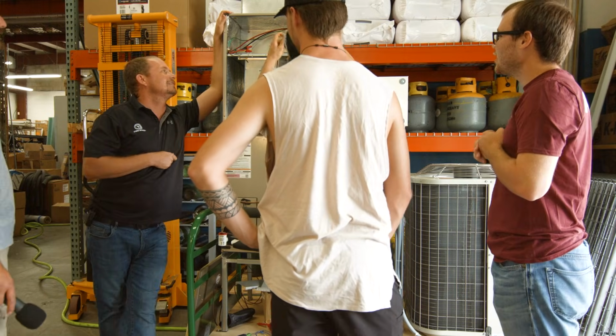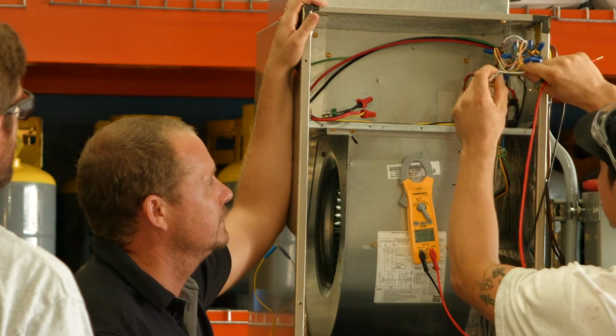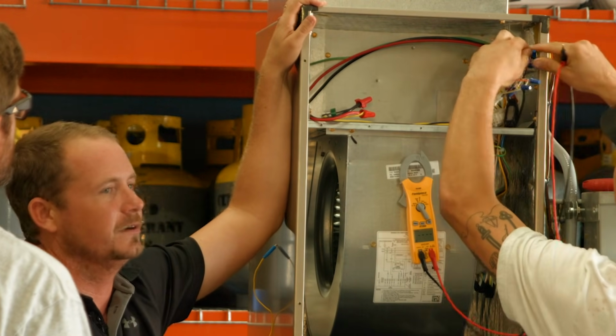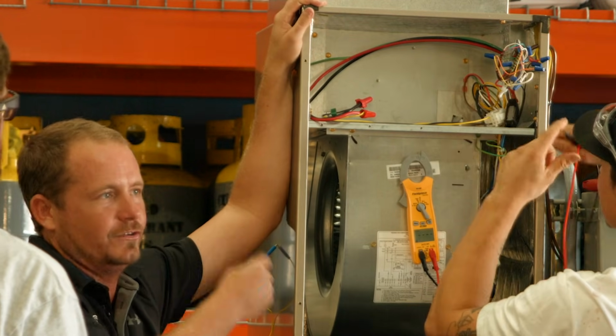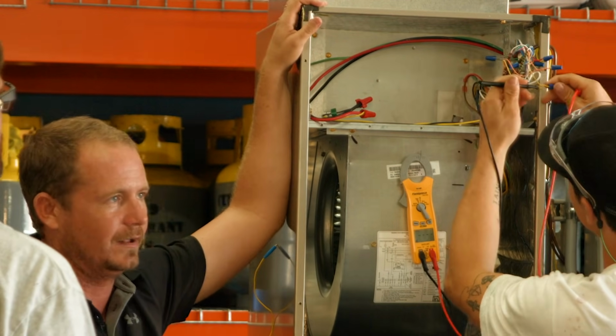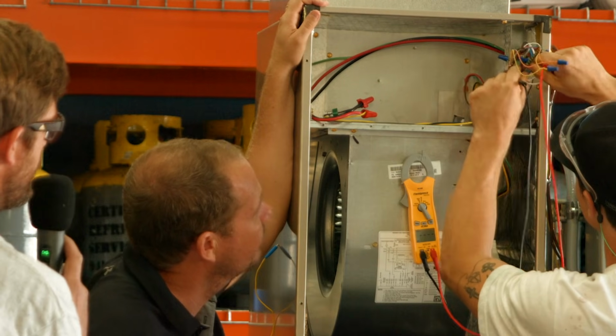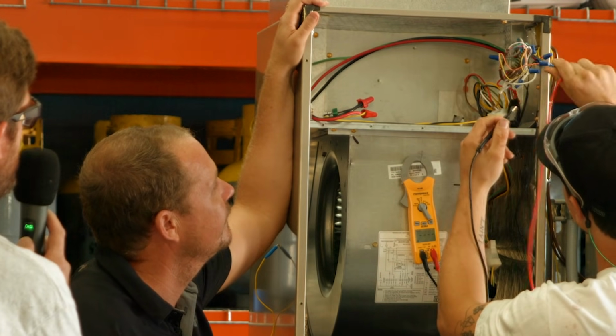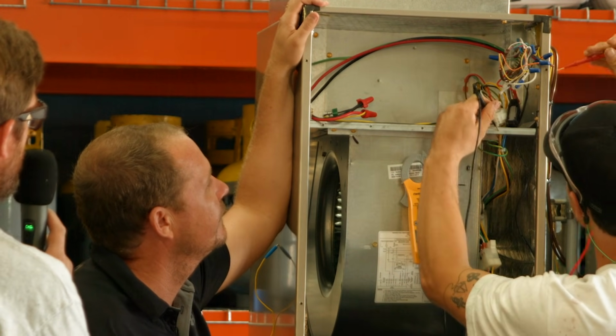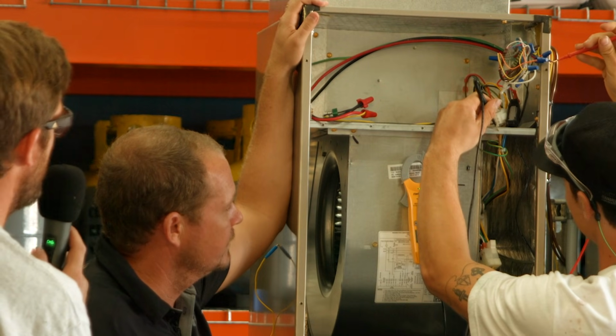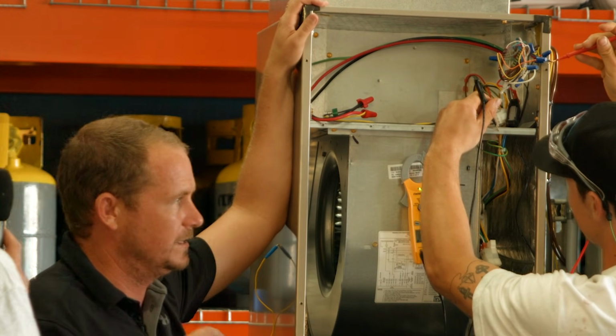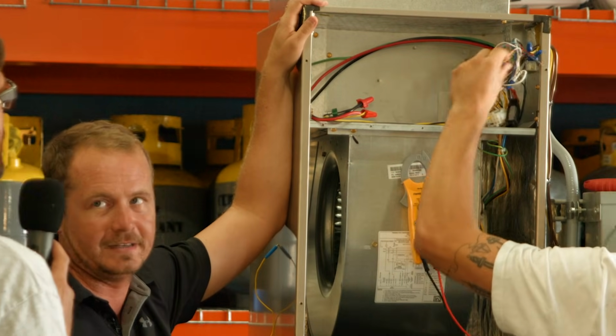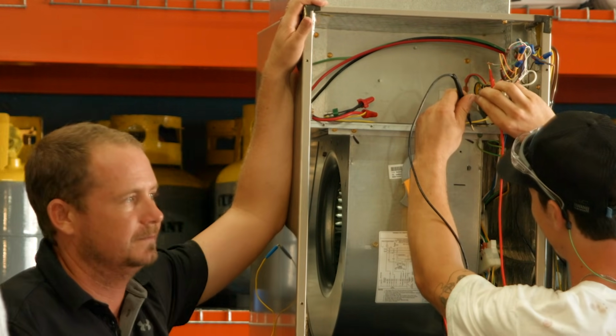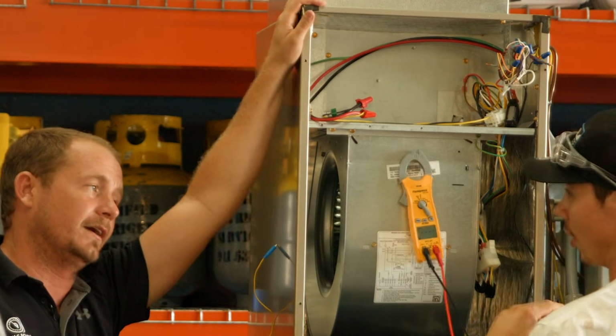Okay, great. So this is the trick, and this is why I don't love this method for a newer tech, is that they've got to make sure that they've got really good connection inside each wire nut. I've already mentioned that. You could take wire nuts off if need be, if you're not getting in there with your meter, and you don't have to pull wires apart though. You could, like he just did there. So that is common. So yes, you're going to get 0 there, because that is common. All right, so what do we got there? We have 1.2. Okay. Very, very low.